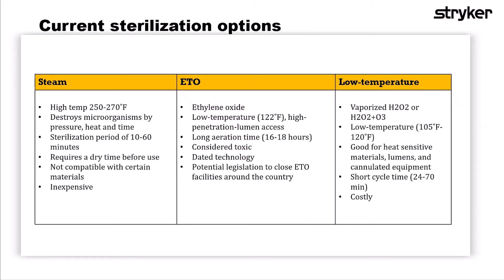Steam is probably the most common modality we see utilized. It uses high temperature — the majority of the time 270 degrees — for a set amount of time depending upon how your steam sterilizer is configured. It destroys all microorganisms by a mechanism of pressure, heat, and time. The sterilization process takes anywhere from 10 to 60 minutes, and that 10-minute period is your flash sterilization process. It also requires a dry time and cooling period afterwards before instrumentation can be used.